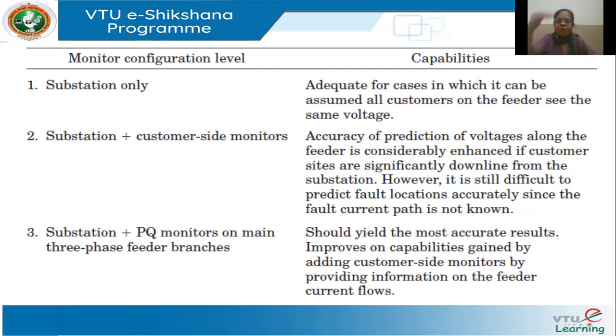But this will fail if I have tappings in between and different customers see different voltage. Or from the same substation, there may be one feeder, one customer may tap at 11 kV, another customer may tap at 66 kV. So in such cases, having just one monitor at the substation is not adequate. Okay. Then substation plus customer side monitors. I place one monitor at the customer side.